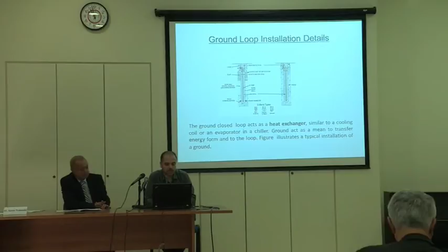To identify the lengths of the pipes that need to be installed, we use the ASHRAE method for estimating the exchange between the pipe and the ground. It is a function of several parameters. The first one is the ground temperature. The second one is the inlet and outlet desired water temperature. The third is the borehole thermal resistance. And what's more important is the annual heat pulse injected within the ground, the monthly heat pulse, and the daily heat pulse, which are RGA, RGM, and RGD.